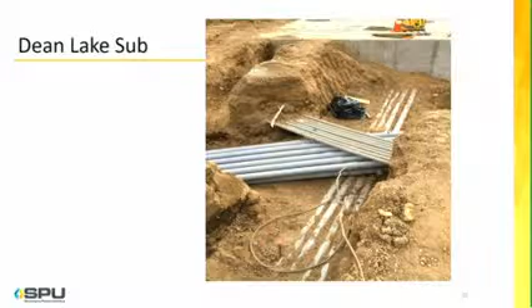This is some of the underground conduit that runs crisscrossing out of the transformer over to the switchgear buildings and back out as distribution circuits. That all has to be pre-installed. This is the foundation work for the control building itself. You can see exit circuit conduits and incoming conduits before the concrete's poured. This is looking west.